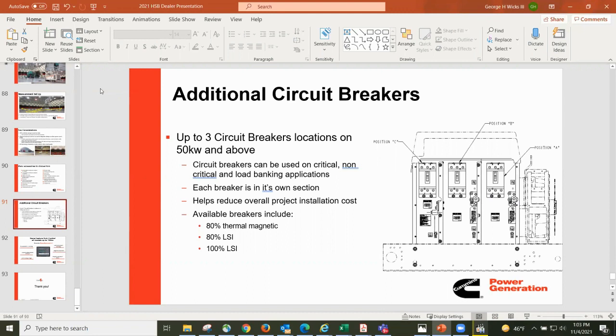Right. Here's what the debate is. We as inspectors in the field want to know because we've seen some gen sets come out where the ampere rating was one thing, and some had 2 breakers on the output terminals of the gen set that added up to 800 amps, and the generator was a 500 amp output generator. Wow. And I'm saying the generator is not protected from overload by the breakers themselves, even though they might have some other internal devices, which would still satisfy the code as far as Article 445.12 dealing with constant voltage generators, because it's your controls that are inherent with the design of the machine. The machine was still shut down because that overload would drive it over temperature, loss of frequency control, all of the above, right?